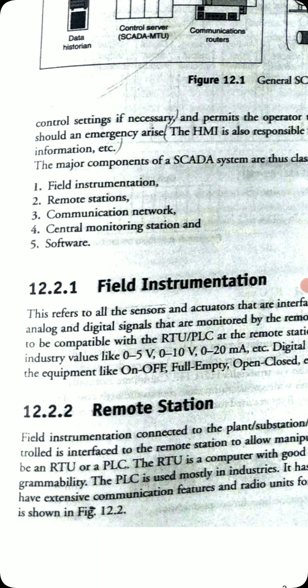Analog outputs of the sensors have standard industrial values like 0 to 5 volt, 0 to 10 volt, or 0 to 20 milliamps. Digital outputs are referred to as on-off condition, full or empty condition, open or closed condition. These are the field instrumentation, which is used to collect the data from the field. These actuators or sensors are used there.